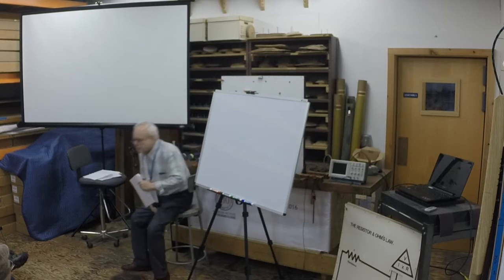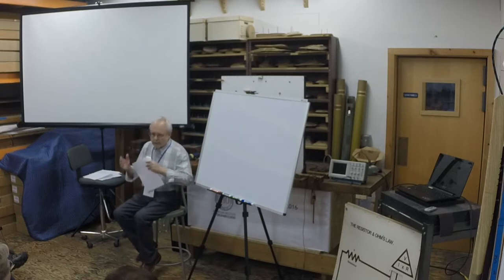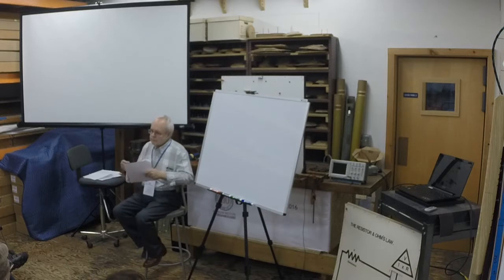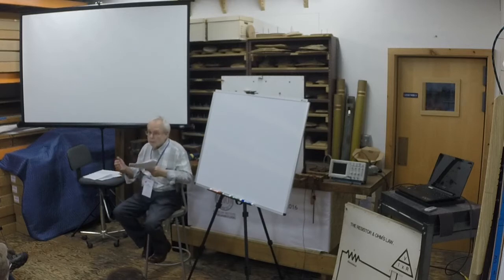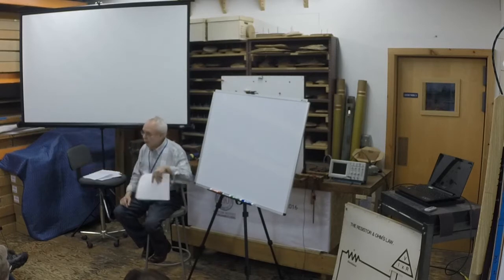these small, rather efficient power supplies are inexpensive and light, but they work on much the same just-in-time manufacturing principle as the automobile factories. They have a small transformer that runs at a high frequency that charges a capacitor, and eventually that current goes out to the organ. But it doesn't store it. It doesn't hold it in reserve. So it's very common for these power supplies, for some reason, maybe Bob can tell us, when you switch them on, even without a massive load connected to them, they can trip a breaker.